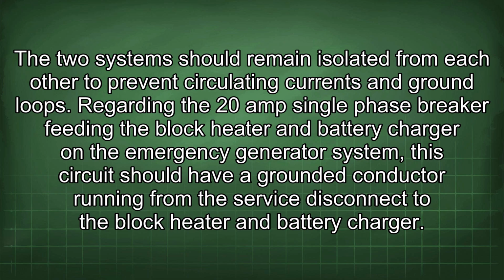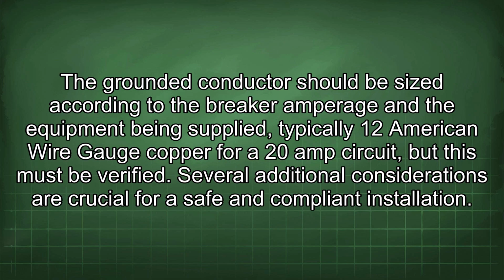Regarding the 20-amp single-phase breaker feeding the block heater and battery charger on the emergency generator system, this circuit should have a grounded conductor running from the service disconnect to the block heater and battery charger. The grounded conductor should be sized according to the breaker amperage and the equipment being supplied, typically 12 American wire gauge copper for a 20-amp circuit, but this must be verified.